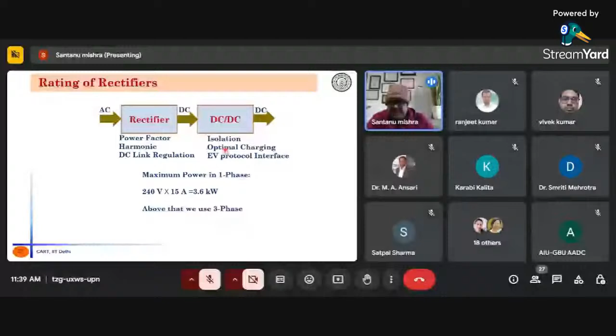Why do we require two stages? The first stage is actually interacting with the grid, so it is taking care of power factor, harmonics, regulation, etc. The second part is taking care of vehicle charging. When you talk about vehicle charging, it's better to go for constant current charging, constant voltage charging, and there are protocols as well. So anything to interface the rectifier with the EV charger is taken care by the second stage. The EV protocol matching, optimal charging which is CCCV charging, isolation, all these things are taken care by the second stage.